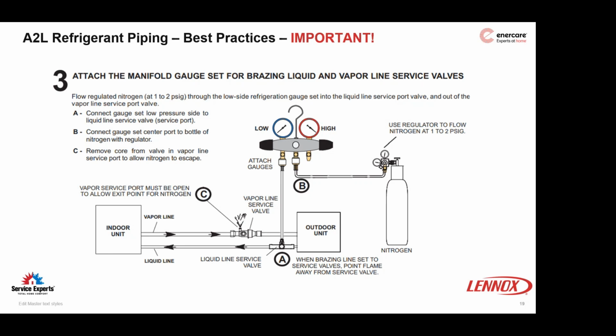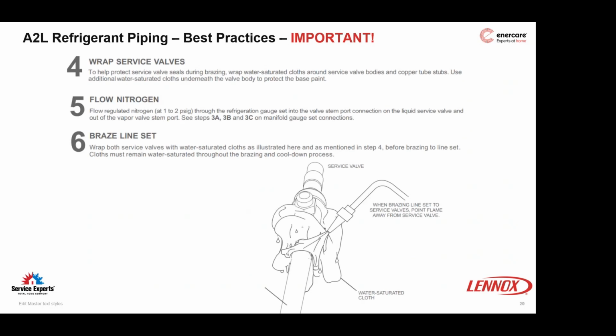If you haven't already, please make sure you're set up with your brazing gloves, safety goggles, hearing protection, and a properly charged ABC fire extinguisher within arm's reach while brazing. With A2L refrigerant on the other side of these valves, keeping these seals cool and protected from any possibility of leaking is a must. We've got to find a way to keep them cold. Pictured, you can see a quenched, wet cloth on that side of the valve to prevent any of those seals from being misshapen during brazing. There's also wet rag putty, which has proven to be effective.